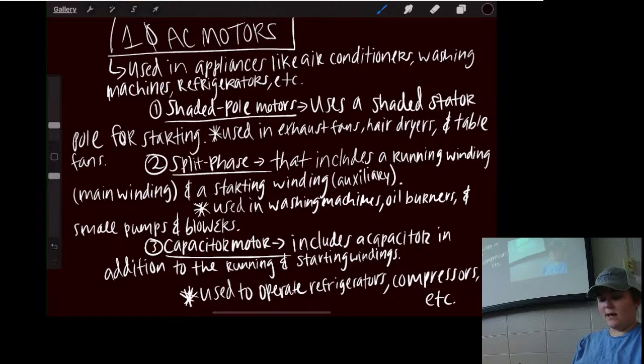Then you have split phase, which includes a running winding, your main winding, and a starting winding, your auxiliary. So what we were just saying was your running winding or main winding would have been your start winding, right? And the other one, what'd you say they called it? Run winding. Wait, no, backwards, I said it backwards. Run winding will be the main, and start winding will be the auxiliary.